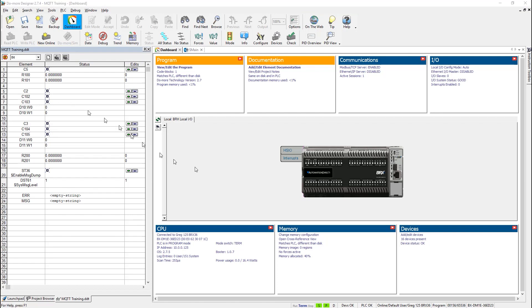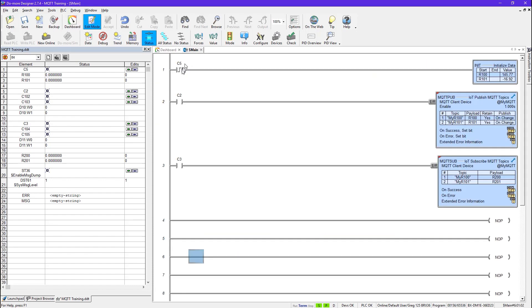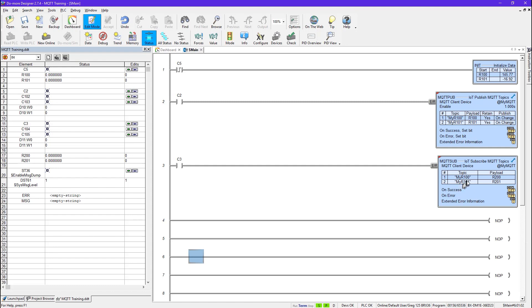Next, after I have configured the PLC, I actually went and wrote a program. It's very simple. Go here to main and you can see I have just a few C bits. And I'm basically going to just initialize R100 and R101 to some values. And then I'm going to use the MQTT pub instruction to publish those values to the broker. And then I'm going to use the MQTT sub instruction to read those back and store them in R200 and R201. So after I execute this, the values that are in R100 and R101 will end up in R200 and R201. And they will be continually updated as I am subscribed to those values.